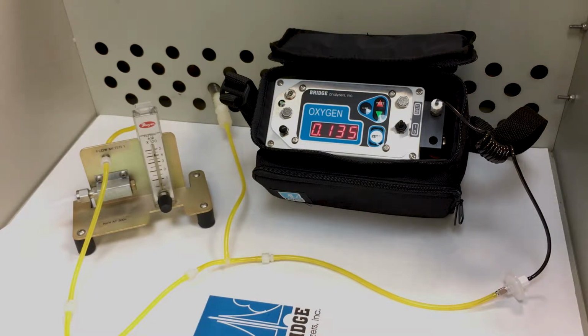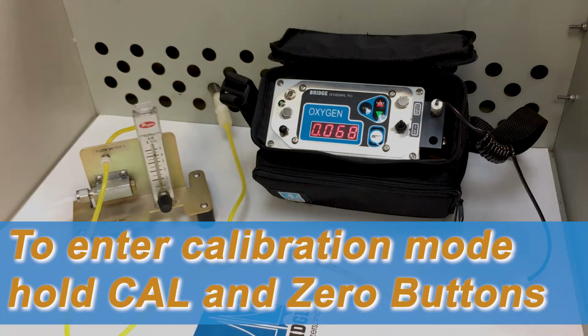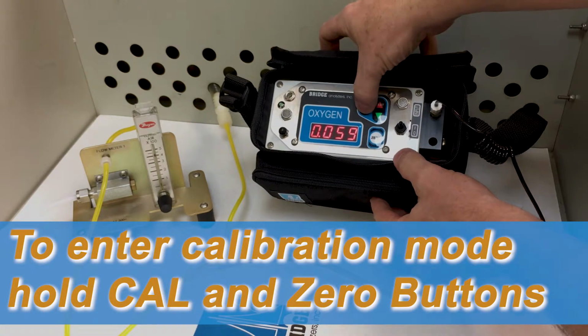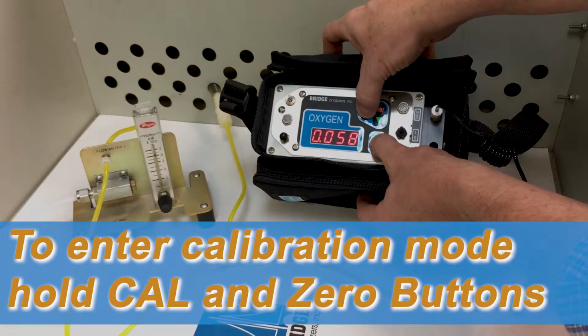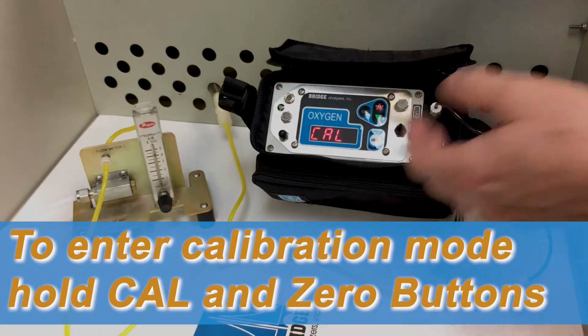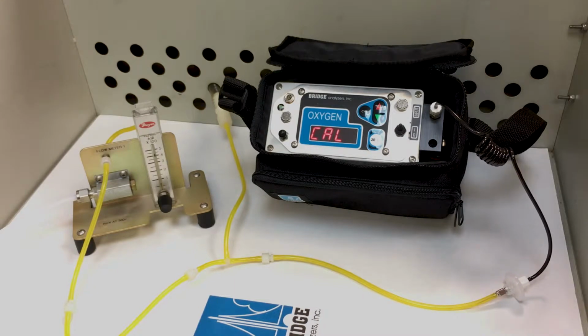So right now we're less than 0.2. We're generally waiting for that to stabilize. While we're letting it stabilize, let's go into the calibration mode. To enter the calibration mode, you press the cal and 0 buttons simultaneously. I'm going to press and hold cal and then hit 0, and I hold them down until it says cal. So now I know that I'm in the calibration mode.